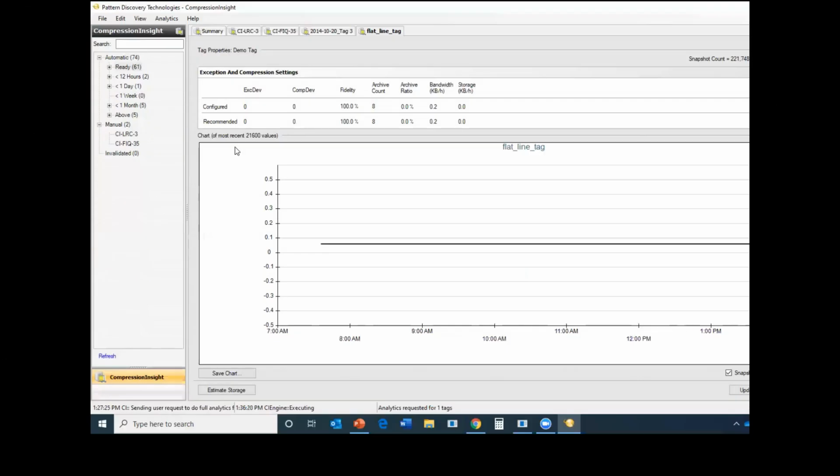What you're seeing is literally a flat line. And so, is a flat line the actual characteristic of this signal? I think in one of your previous videos, Jim, you showed a case where a level gauge or a temperature reading, I'm not sure which, had actually flatlined based on a problem with information coming from the interface. These are all useful pieces of information to tie together to ask, am I really getting the information that's being stored?